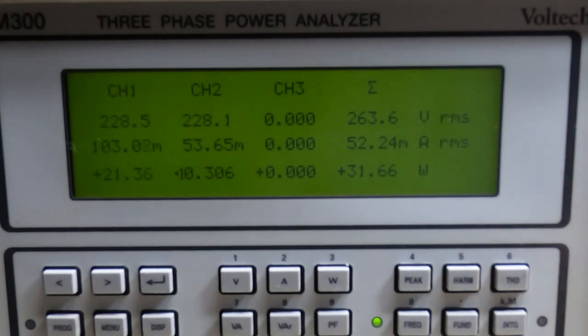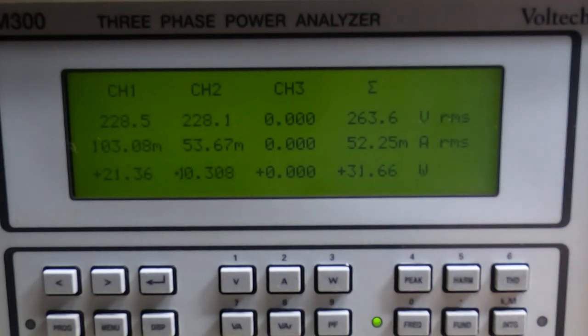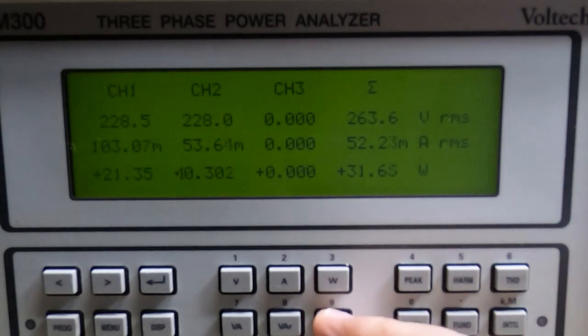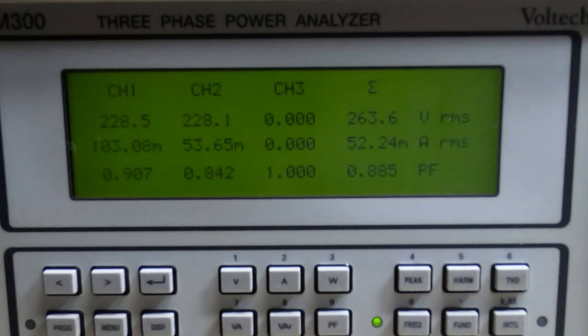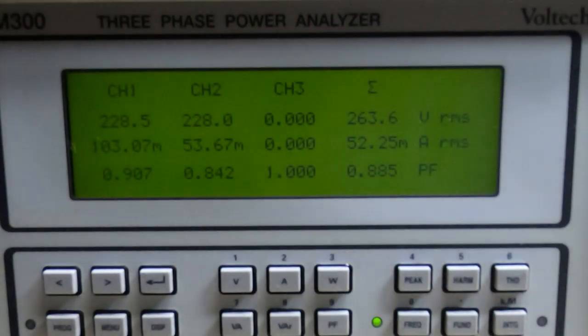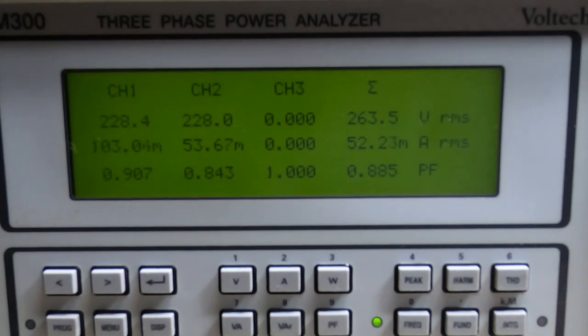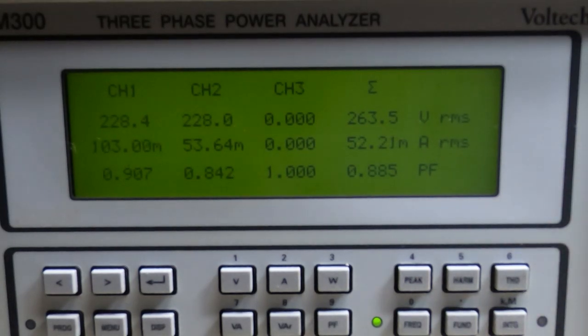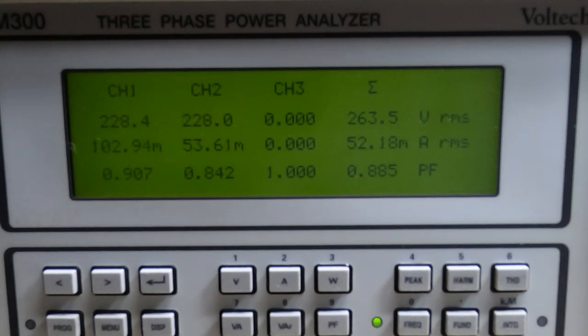And if we now go to power factor, again we're seeing very comparable results to what we were getting before. So you can see the PM300 is truly isolated in terms of its electrical measurement characteristics and it can even monitor its own power usage.